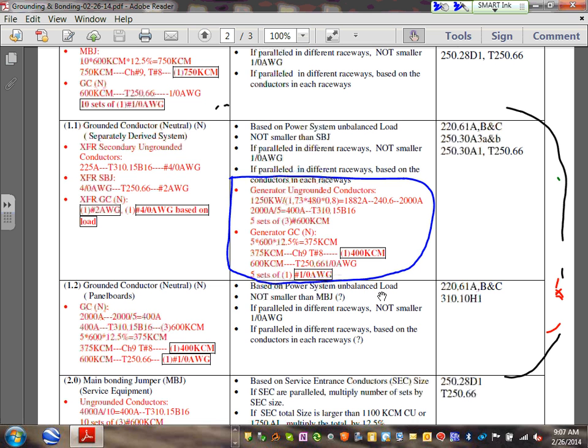To size the neutral for the generator, I need to size the ungrounded conductor first. So I have the generator ungrounded conductor. I have 1250 kW divided by 1.73 times 480 times 0.8. What's the 0.8? Power factor, assuming a power factor of 0.8. That finds the amps of the generator. You got yourself 1882 amps. That's a big boy. Since it's in the thousands of amps, we don't multiply by 1.25, because we assume the overcurrent protection devices are 100% rated, like these 100% rated circuit breakers. So we take the 1882 to 240.6, which gives you an overcurrent protection device of 2000 amp.